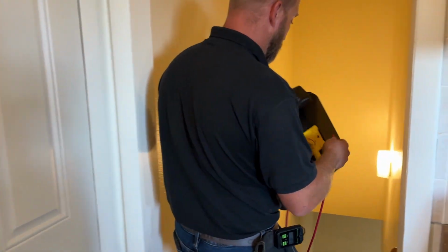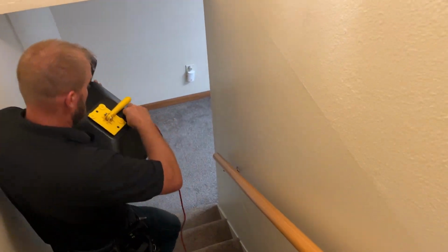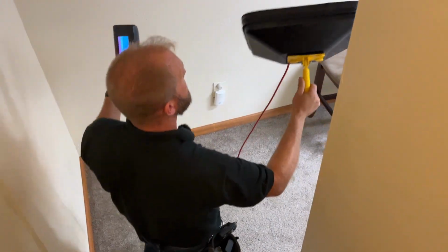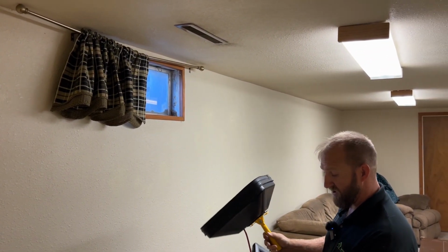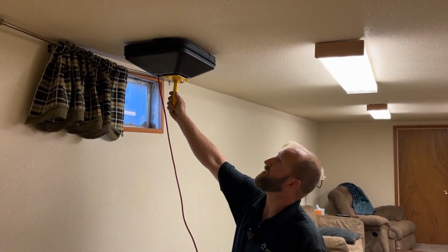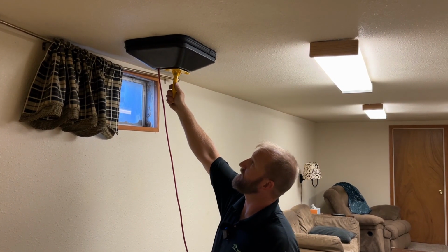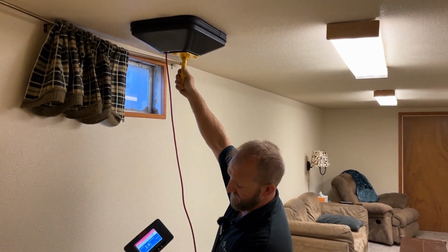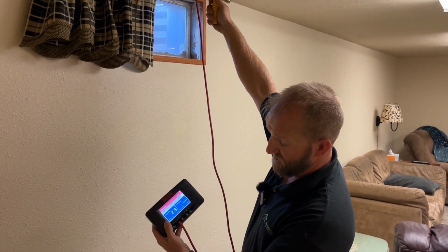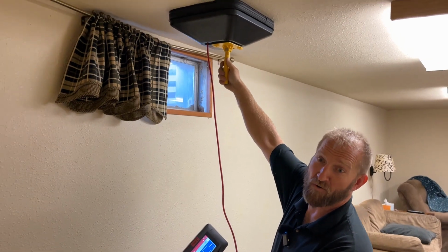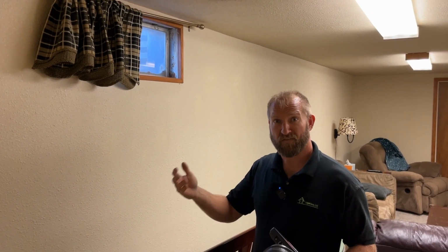So the easiest one to do on here is down in the basement. You want to have this on your input here. You're going to come in, cover the entire thing, press firmly, and you can see that it's pressurized in there. So this one's pretty leaky. We might want to note that we can do some duct sealing that can reduce the leakage in the house too.